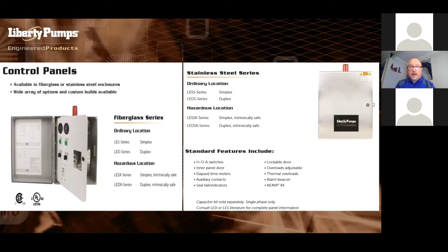We are offering these pumps in single phase up to 5 horsepower. Majority of these, specifically the dual seal pumps, are external capacitor driven. So you need to order an external starting kit, start capacitors, run capacitor components to go with that. There are a few of the single seal models that you can order with an internal capacitor setup.